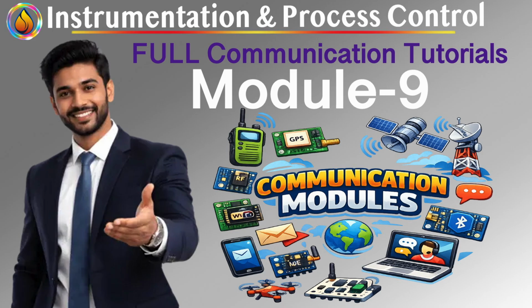Here's the key shift in thinking. Open quote, "Device count is not limited by protocol. It is limited by voltage at the farthest device." Close quote. You can stay within every standard limit and still fail, silently.